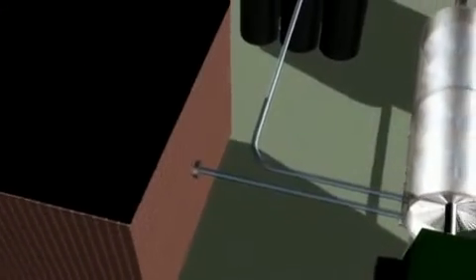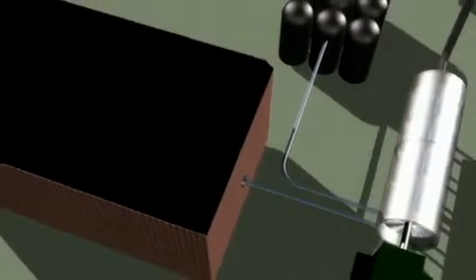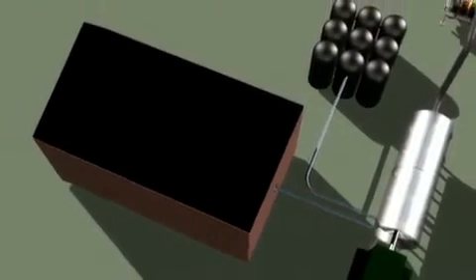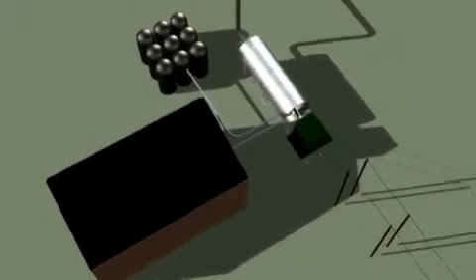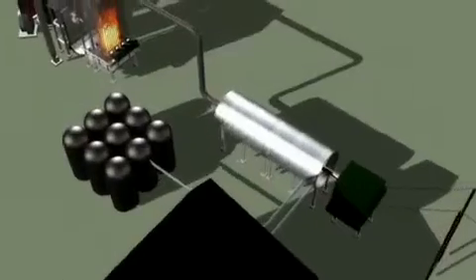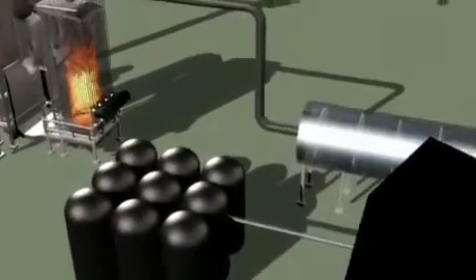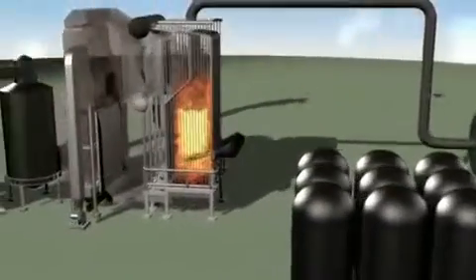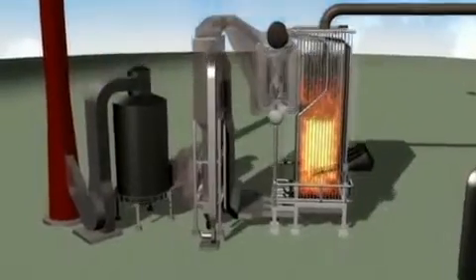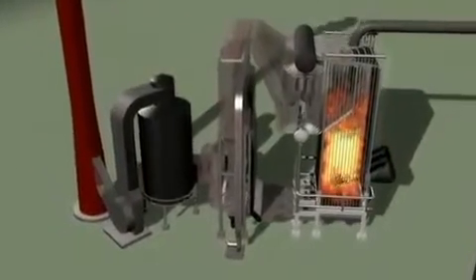On leaving the turbine, the steam still has a temperature of up to 300 degrees Celsius and a maximum pressure of 11 bar. Separate pipeline systems feed this steam to the reactors or to the pigment drying facility. By commissioning this cogeneration plant, the Portofilis site will be able to do without fossil fuels altogether.